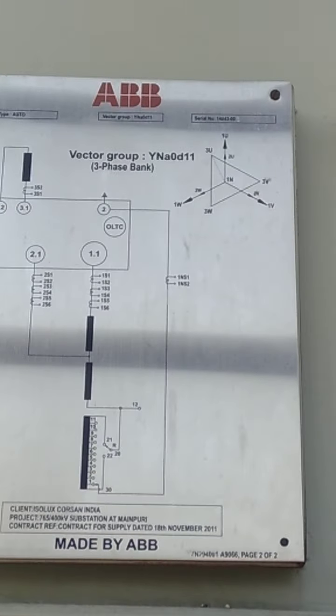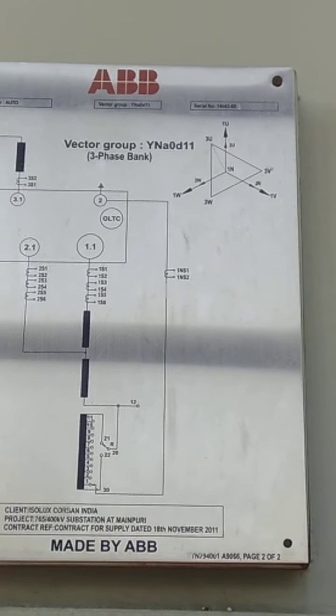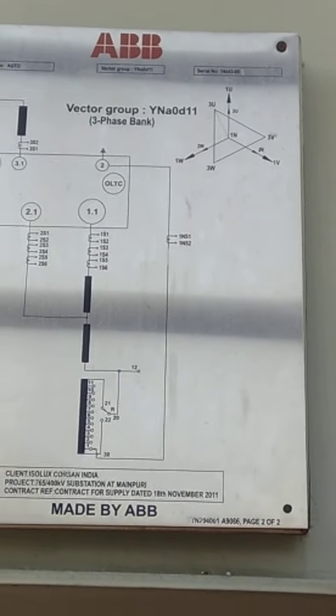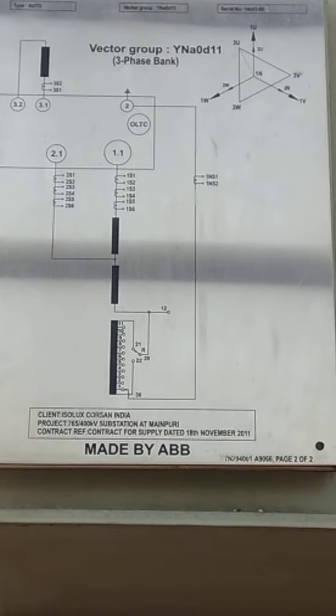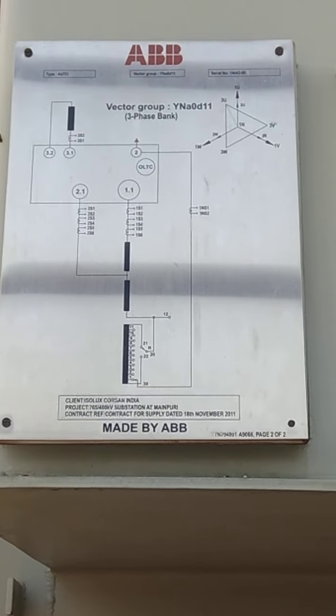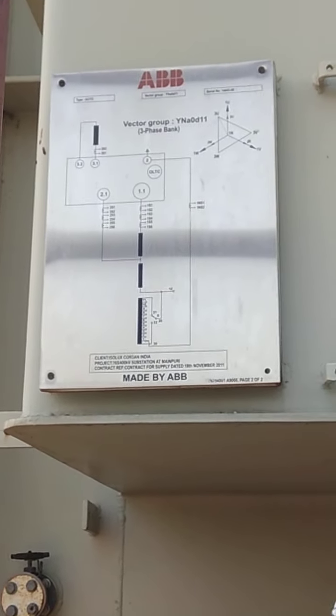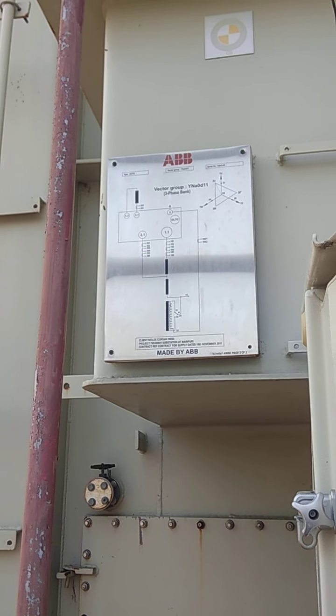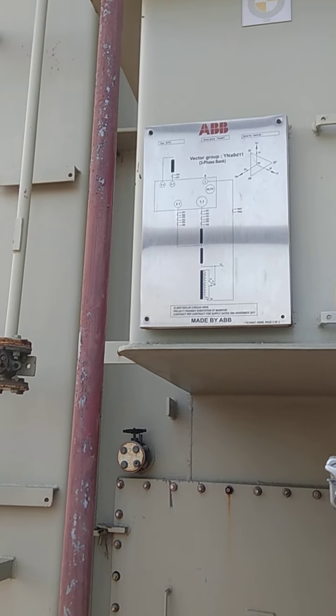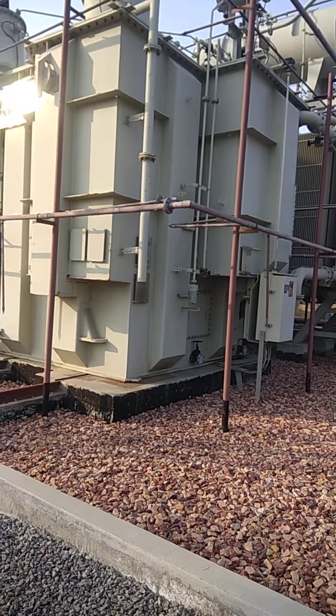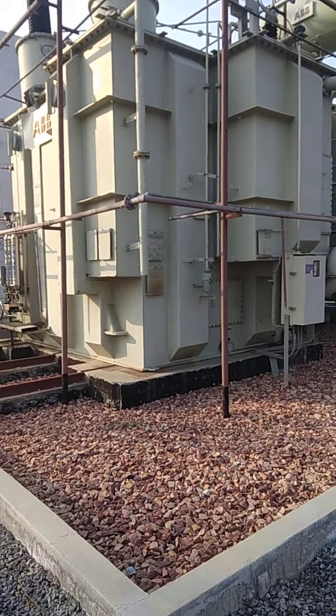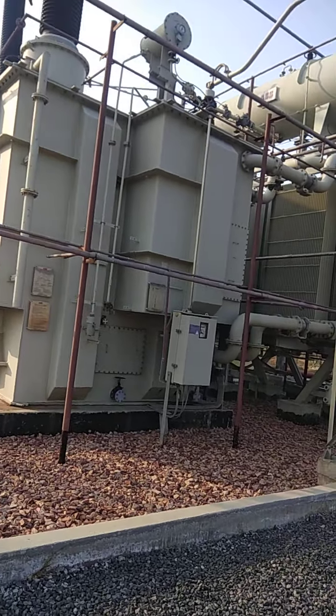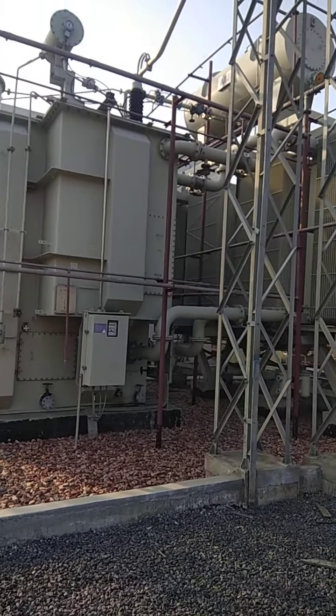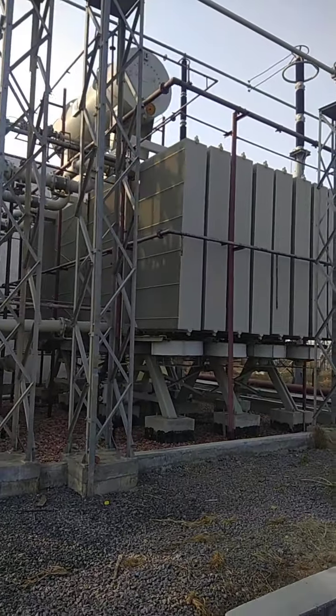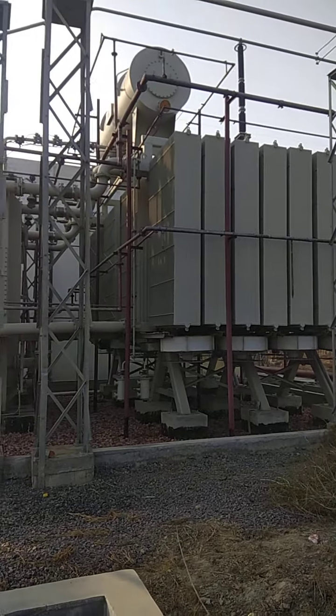As you can see, this is YNa0d11. Also for single phase units, the synchronization of OLTC is a big challenge because each unit has an individual OLTC. As you can see, the size of this transformer is very big. This is a single unit of 333 MVA, and the combined unit of these 3 units is 1000 MVA.